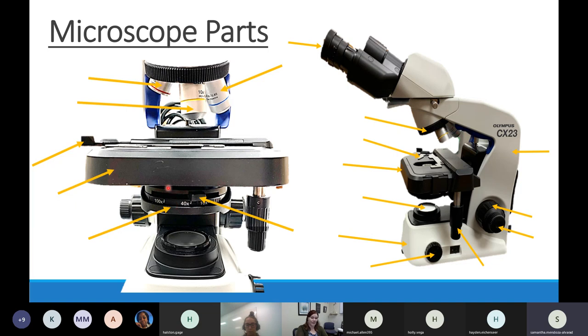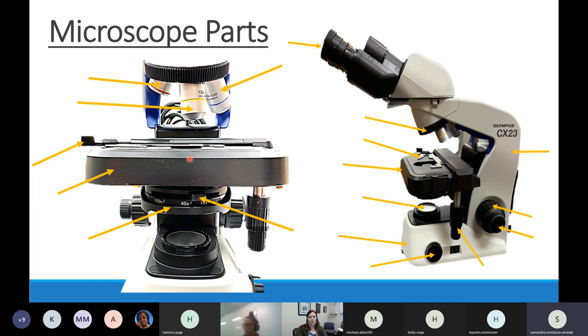Something we can't label in our picture because it's hard to see, but you still need to know about: up higher than the iris diaphragm but still below the stage is something called the condenser. The condenser takes whatever amount of light the iris diaphragm let in and focuses it onto the slide. So the iris diaphragm controls how much light gets in, and the condenser focuses that light. Both impact the way you view something on the slide.